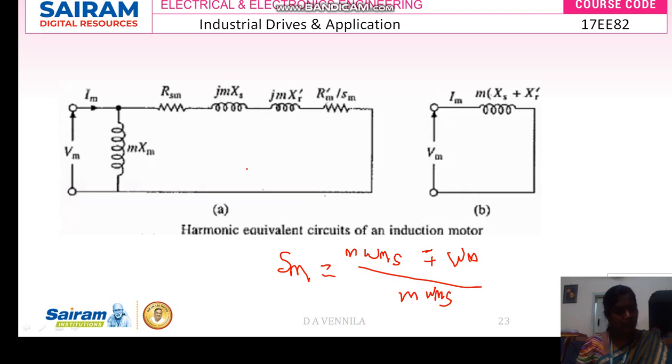Due to magnetic interaction, the current flow takes place only at the surface of the conductor, not beneath it. The skin effect is mainly due to frequency. If the frequency of the supply is more, then the skin effect is also more. So this will create a several times increase in resistance. We know that the reactance is increasing by the factor of m.